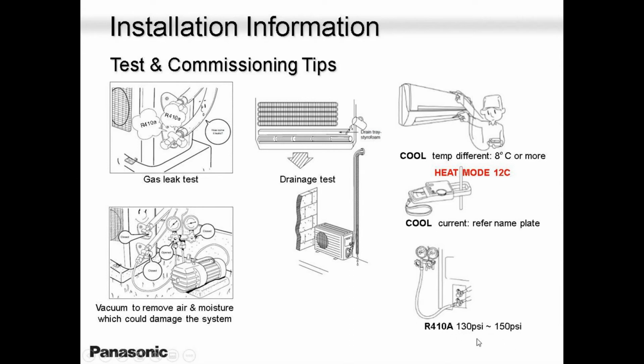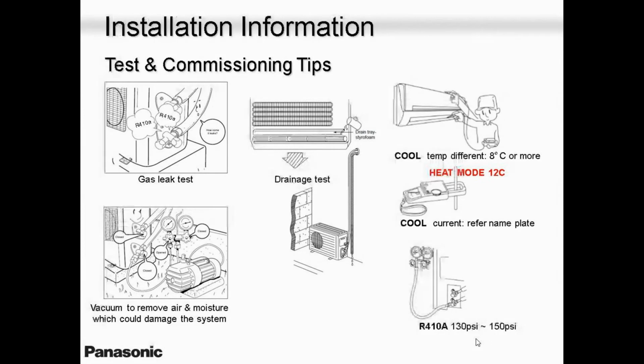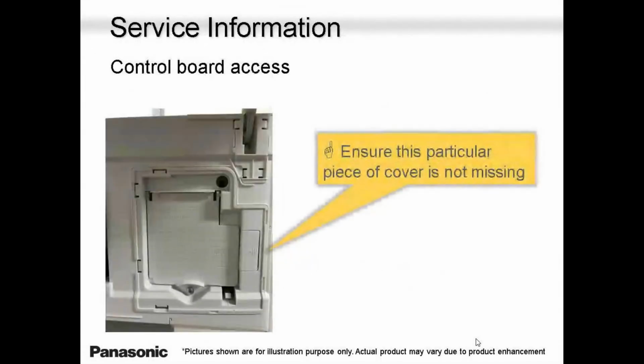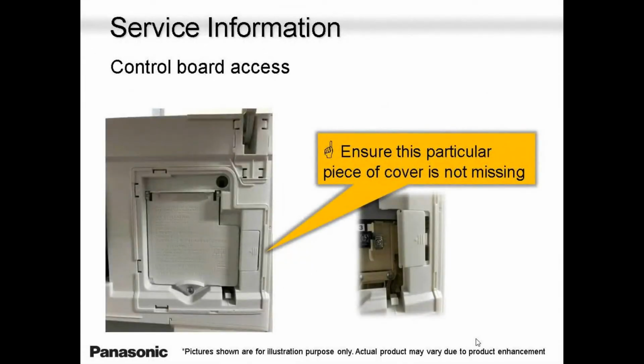After that, they vacuum the system, they turn on the unit, it is running, they sign the papers, they got their money, and they're gone. After a couple of days, the homeowner is calling, the unit is freezing when it comes to heating. Or it's not cooling enough during summertime. Why? Because the guy, when he was vacuuming, he ran away with some of the Freon. So please don't pressurize the system too much. Just enough to check your leaks and you're good.